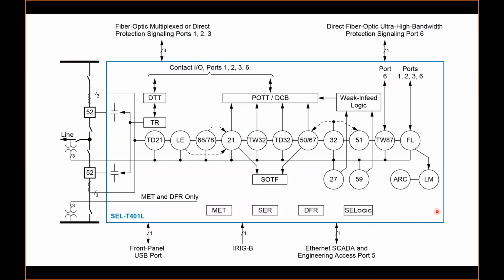So this is the functional diagram in which you can see some conventional elements: phasor-based distance, power swing elements, load encroachment, directional elements, phasor-based 51 backup overcurrents, and some voltage features. And the new technologies as well, like TW87, TD21, and the directional elements based on incremental quantities and traveling waves. And similarly, we have fault location that is using the double-ended or the single-ended traveling wave fault location methods, plus the conventional impedance-based methods are also available. Line monitoring and auto recloser control. So these 5 elements are the core to the modern power systems.